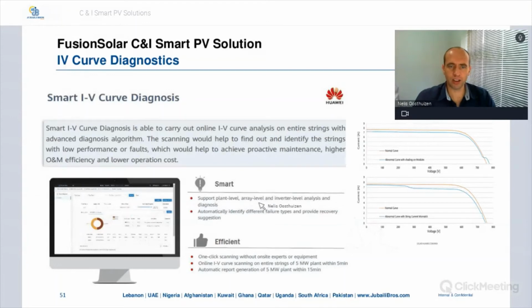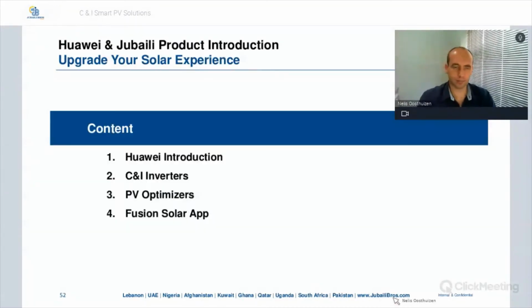It supports plant level, array level, and inverter level analysis and diagnosis. It automatically identifies different failure types and provides recovery suggestions. It's efficient as it's just one-click scanning. It's done online, and the report is generated automatically within 15 minutes for a plant of about 5 megawatt.